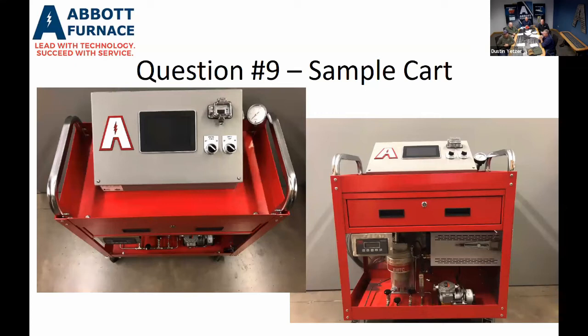And if you're still having problems and you've got discolored parts anywhere throughout the furnace, we will have our technicians come over with that cart to make sure you've got the right dew point and the right oxygen levels, and make sure the hydrogen's going where it's supposed to, front and back, so we have an equal balance of that furnace to get a desired product off your belt. We can also mention that these aren't just parts that we take in, these are for sale as well for inside of your facilities.